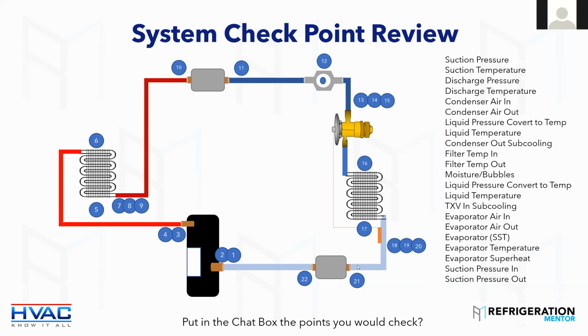Yeah, right. Remember we went back a couple days, like a day or two, and changed it out. And now it's just sitting there, it's piped in extra and it's just blocked off on this one. Yeah. So you want to make sure that you go look at Sporlan, you'll go look at Alco or White Rogers, you'll go look at Danfoss, and you'll read their manuals, and they're going to say they want you to change that after a certain amount of time.